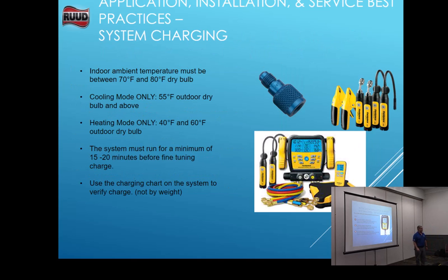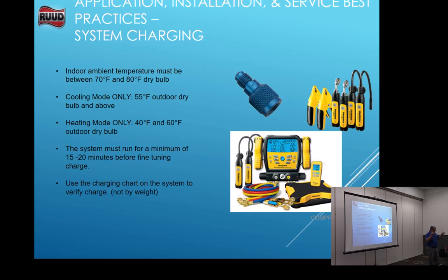The tools that you see up here are all Fieldpiece. I like Fieldpiece. Don't care what brand of tool that you buy. But digital is where we are. Analog is just not going to cut it in today's equipment with the accuracies that we have to have with the charge and airflow and everything going forward. Does everybody in here own a manometer? We do now. Okay. Hey, one step, you know. You got a Christmas present one year, you know what I mean? You know, they're a great tool to have. You've got to have them to check static, okay? We talked about airflow, so that static pressure is going to be critical going forward for systems. Did everybody know when you put in a gas furnace, you're supposed to check the gas pressure? You go, well, why? Isn't it already set?